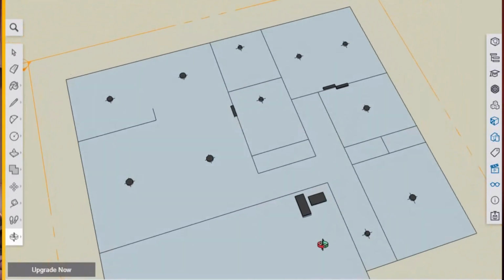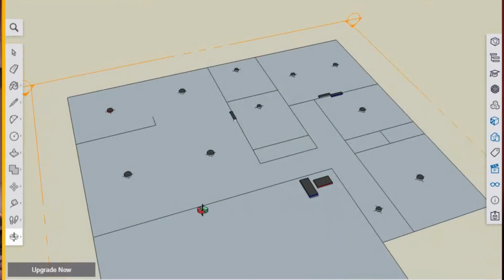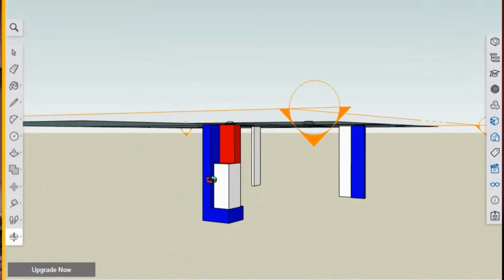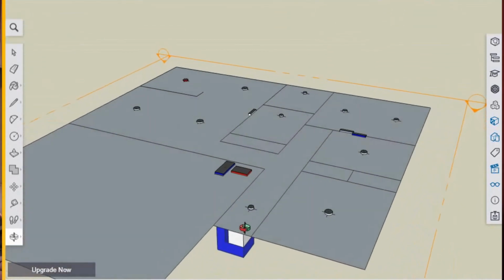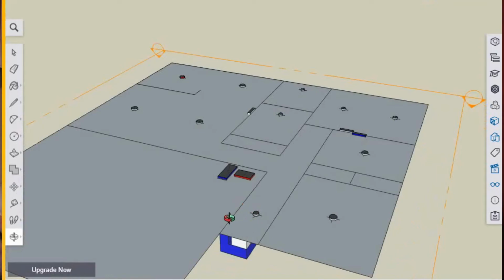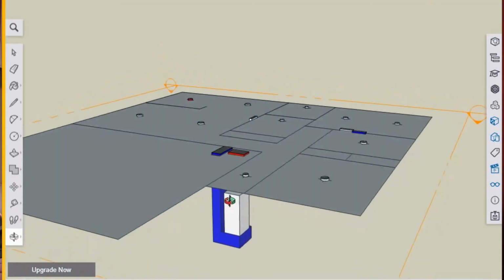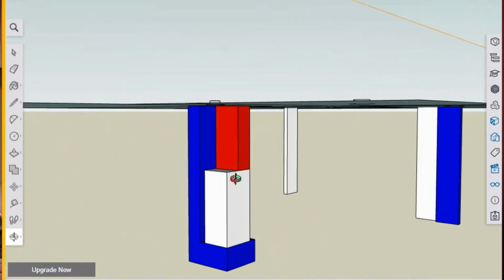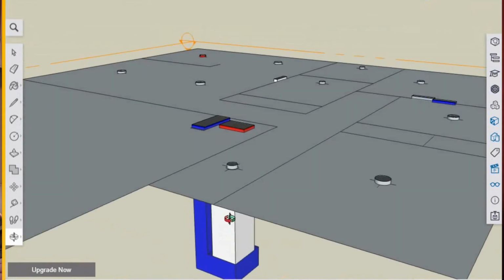Now, what I would probably have done, as opposed to putting a horizontal air handler either up in the garage roof or in the actual ceiling or the roof line of the house, I would probably put the equipment down in the garage itself. That way you can actually maintain this thing, okay? You can work on it, because nobody likes to crawl up in an attic when it's 130 degrees and try to work on something that is squeezed in between rafters and 3 feet of insulation. So this is where I would stick it. I would stick it down here in the garage. You would lose about 2 feet of the corner, but hey, so be it.